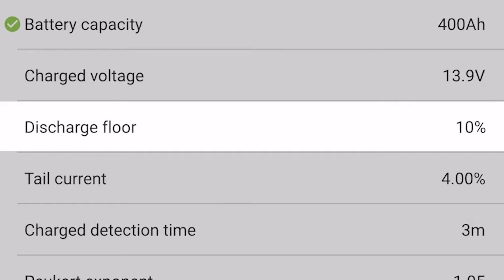So what that's telling the system to do is to calculate the battery percentage so that when it gets down to 10%, that would be considered empty. And this just allows you to have a little bit of room for error. If you are draining your batteries all the way down, even when you get to 0, there still should be some capacity in the system. And it's really not a good idea to run the batteries all the way dead, because at that point, since none of the equipment will start up, you can't even charge the batteries with the inverter. You actually have to put a battery charger on the batteries first. So it's a good idea to always keep some power in the batteries.